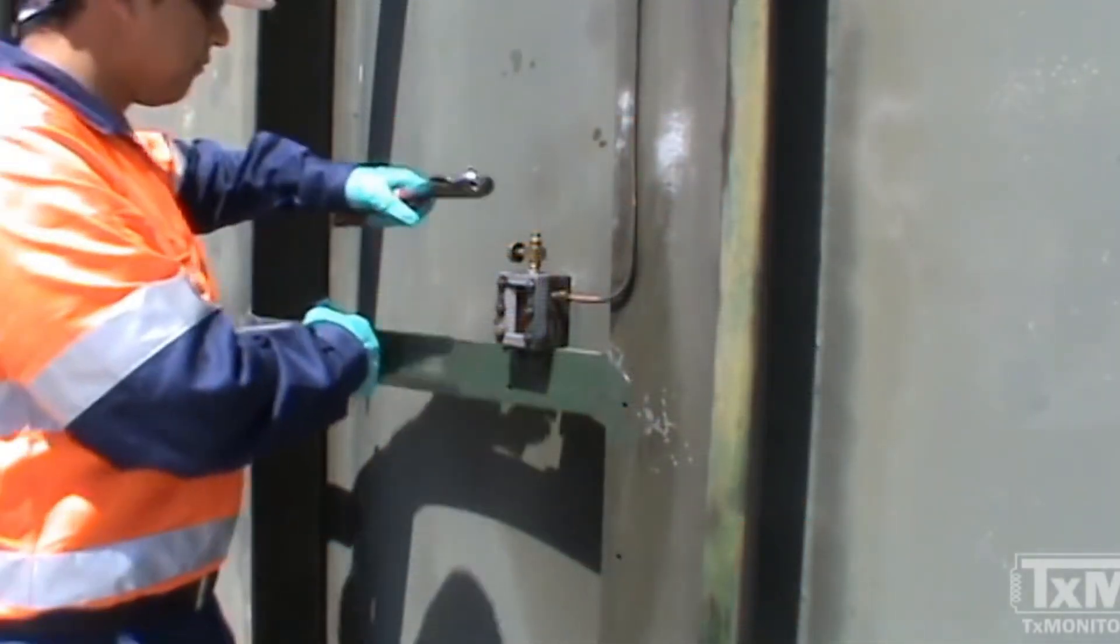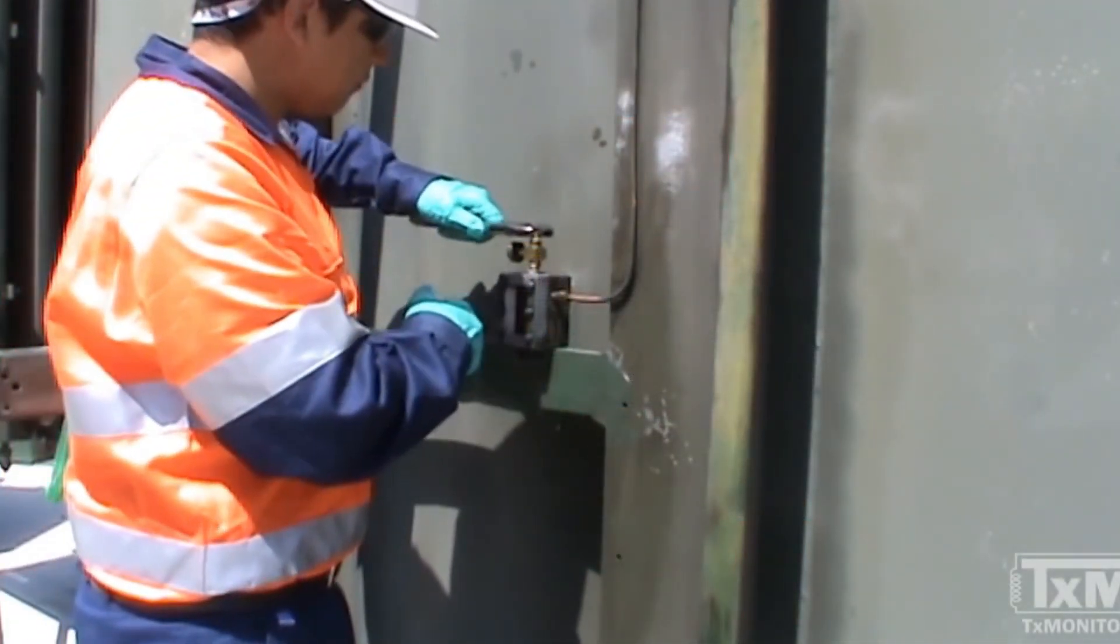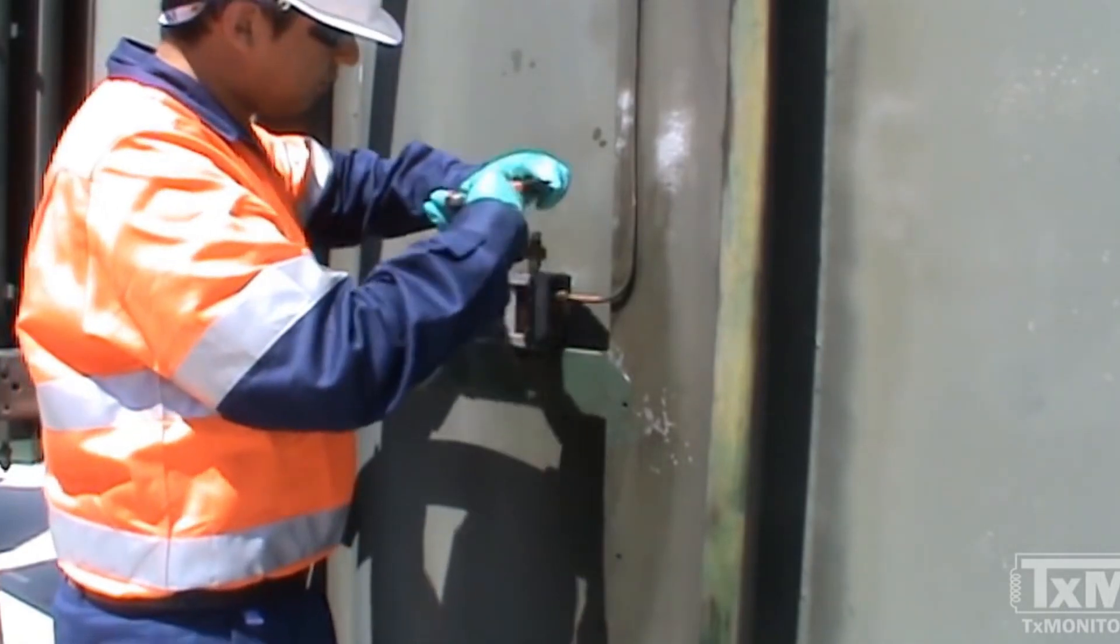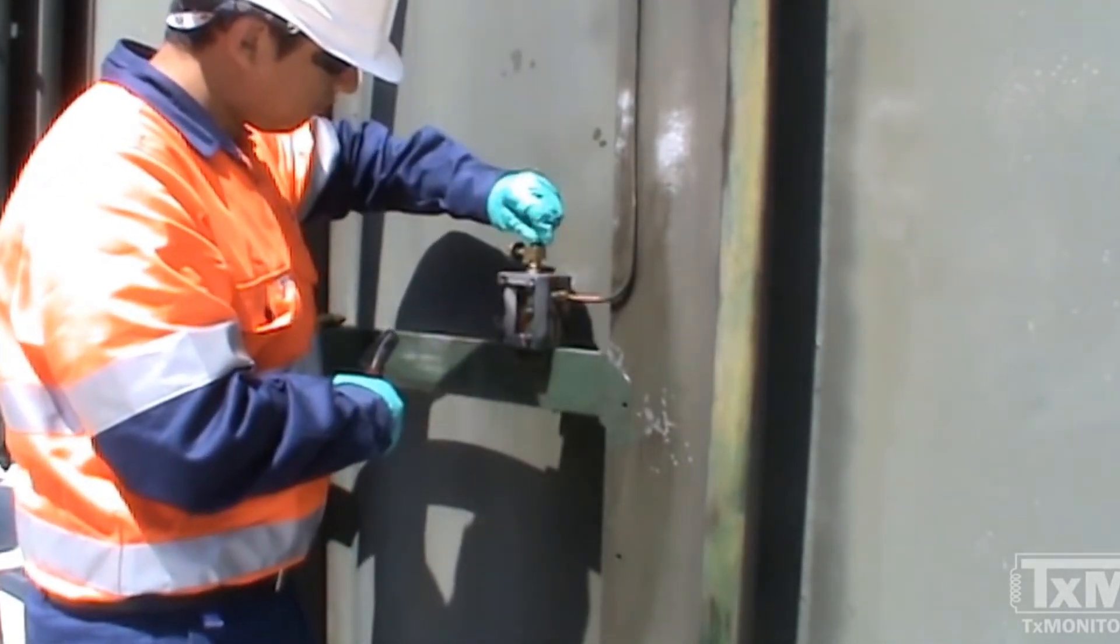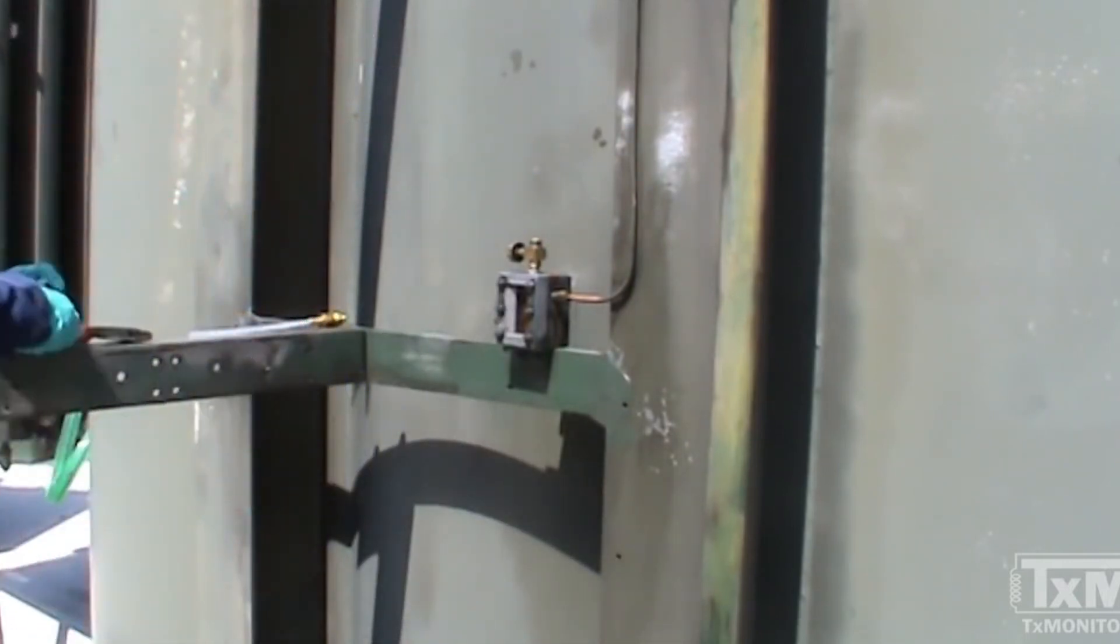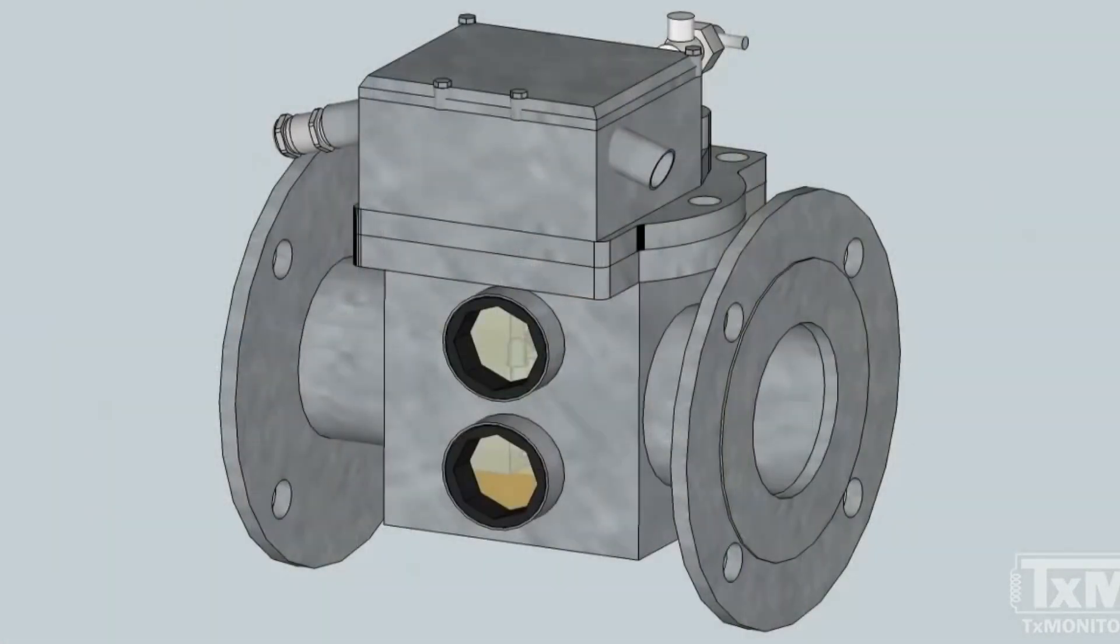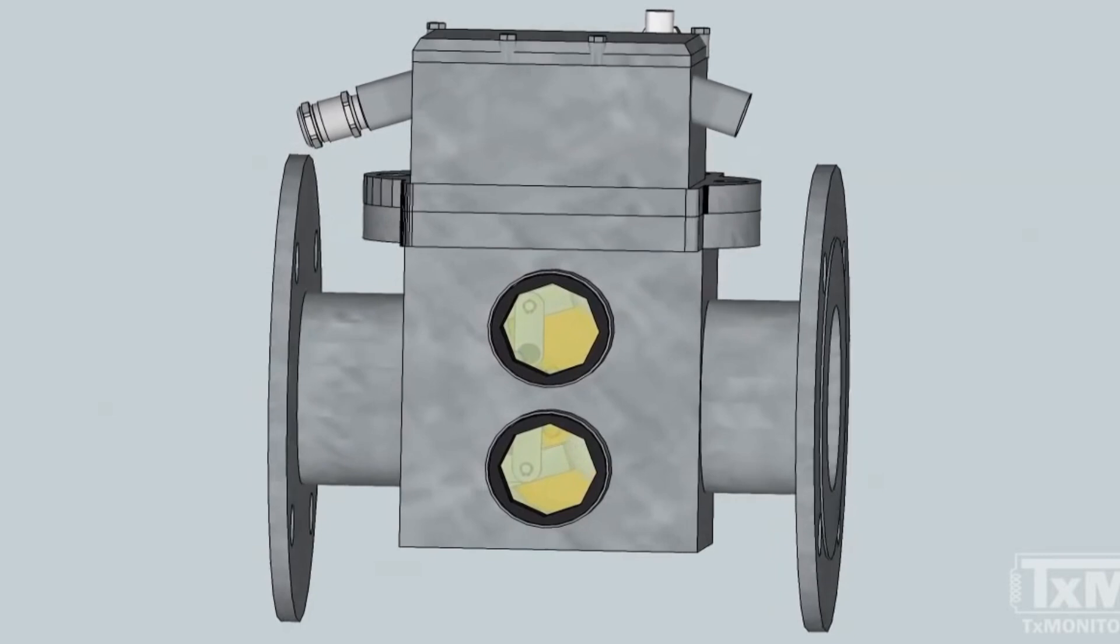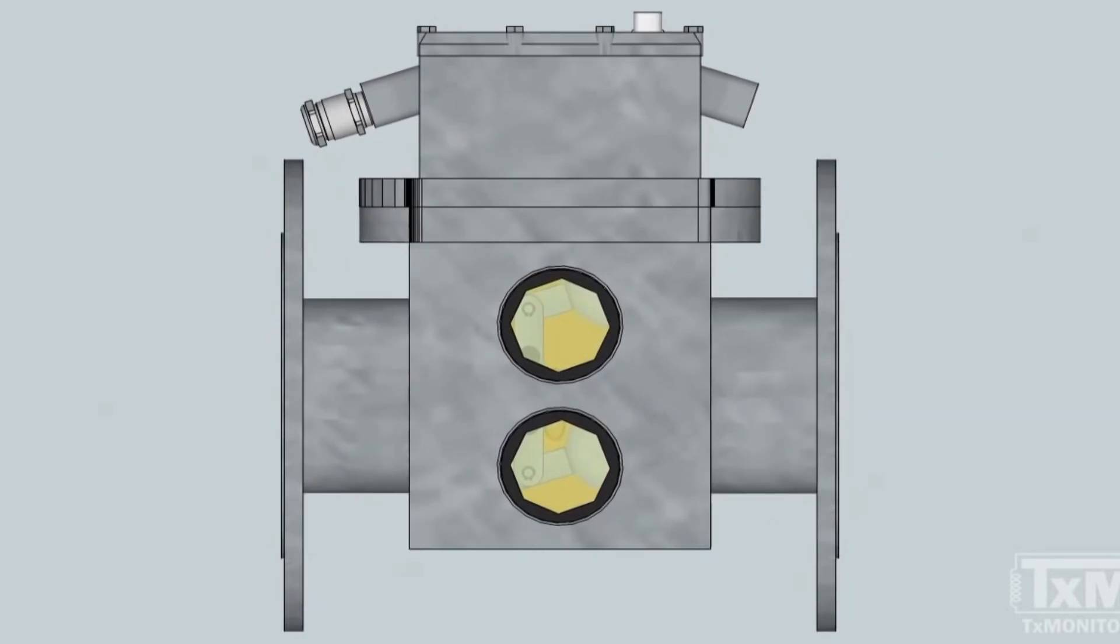The Buchholz samples can be taken from the gas sampling device accessible at ground level. If this gas sampling device is not available, the samples have to be taken directly from the Buchholz and therefore cannot be taken while the unit is energized.